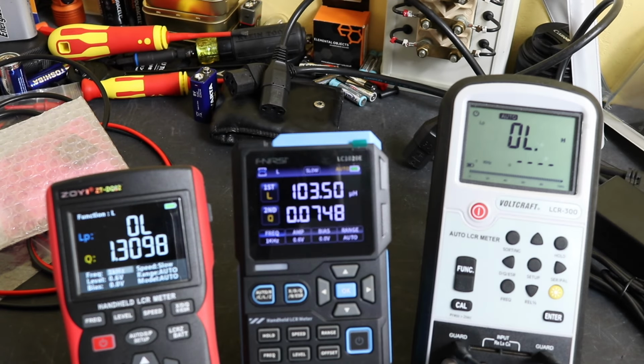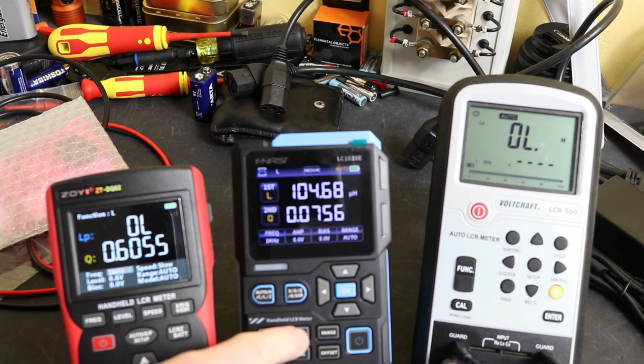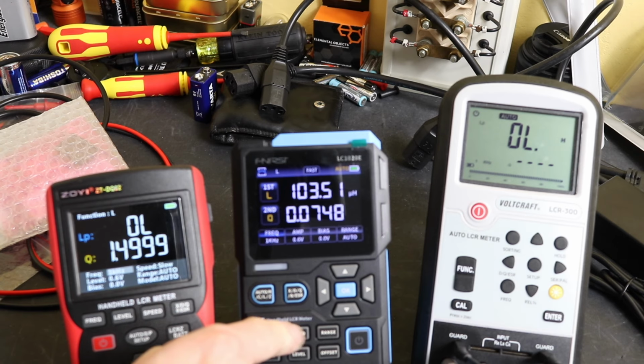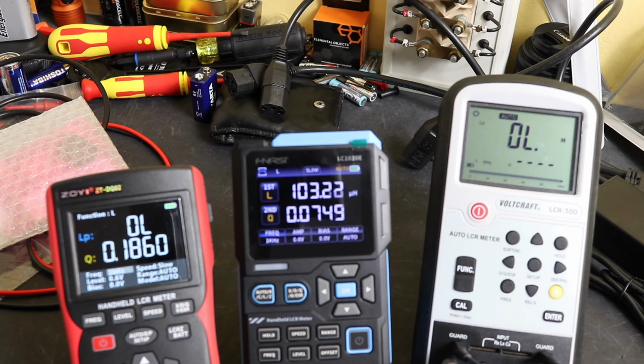Now when I first set this up, you can see I now have it switched to slow. Somebody pointed out to me on the original video that I had this set to medium speed, which does make it more erratic. That's medium there. So you can see the reading's a lot more erratic. That was my bad. We go to fast, it gets even more erratic. Well, we go back to slow and you can see it steadies the reading down. So that solved one of the problems that I had specifically with the Fnirsi unit.